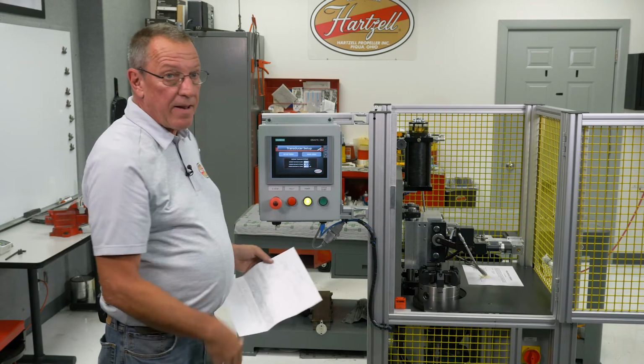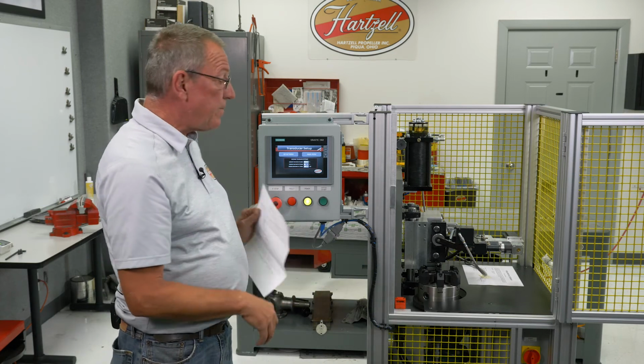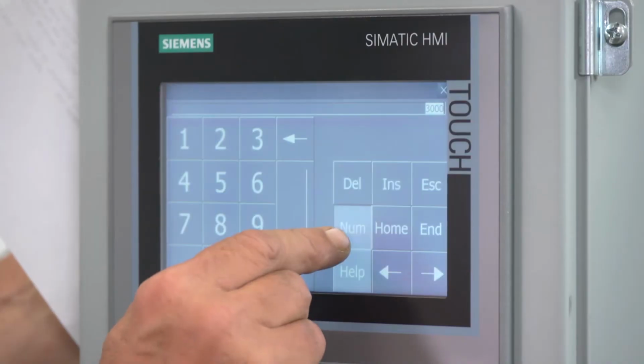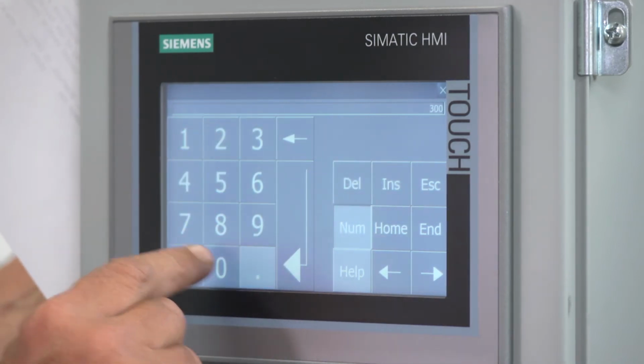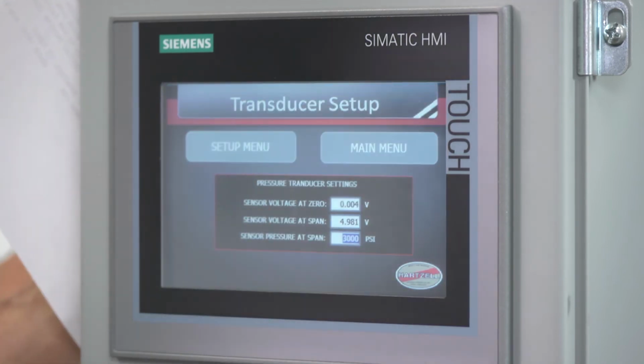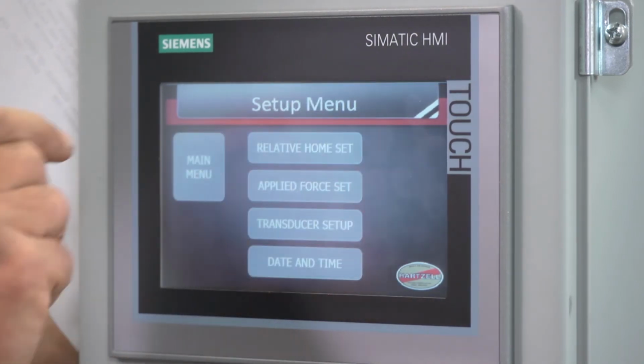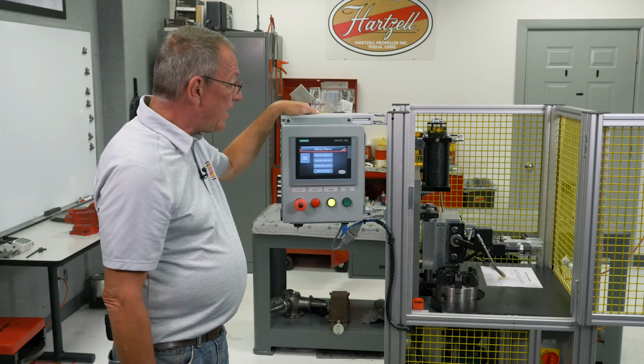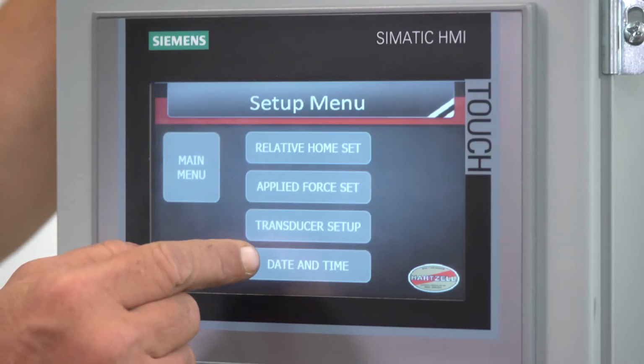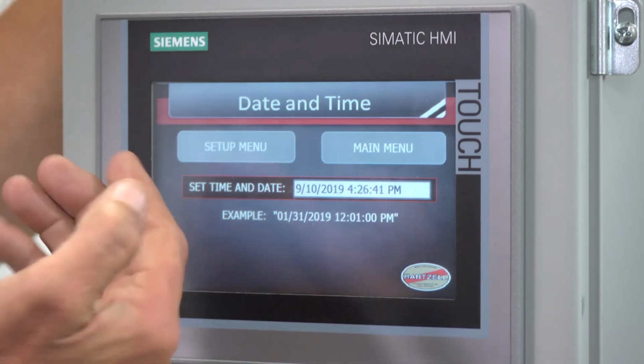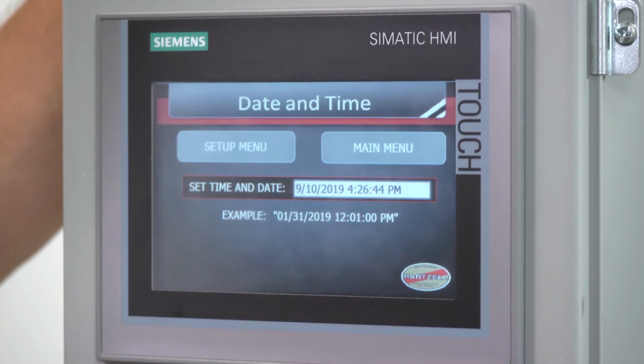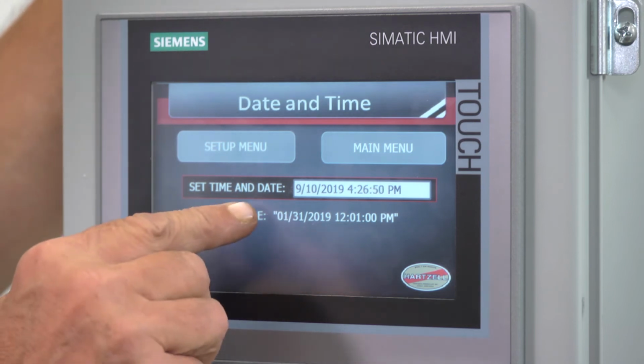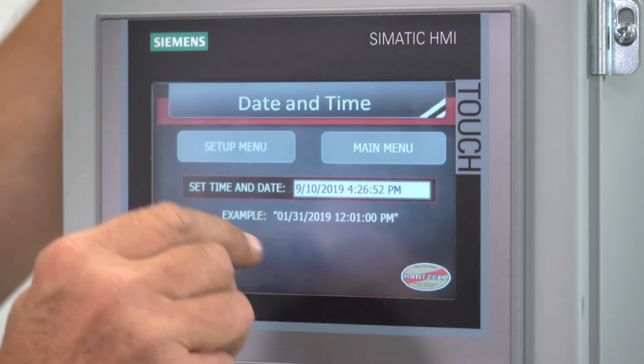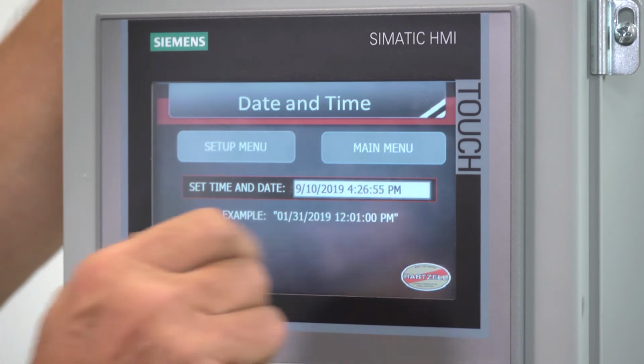Sensor pressure at span. That's at max PSI, 3,000 PSI. So I want to make sure my sensor pressure at span reads 3,000 PSI. And I'm finished. The final setting is to set the date and time. So we'll press date and time. And this date and time is set correctly for today. I just want to note the format. The format is the month, the date, the year, and then the time.